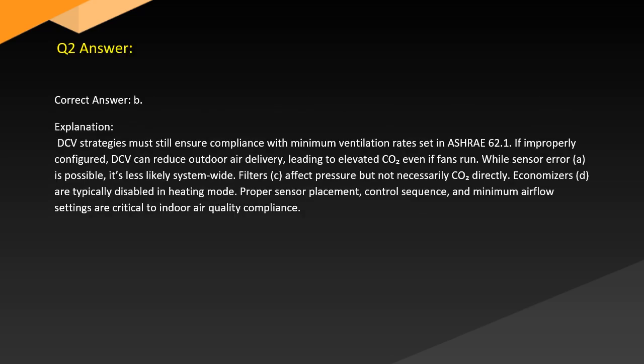Answer. Correct answer: B. Explanation. DCV strategies must still ensure compliance with minimum ventilation rates set in ASHRAE 62.1. If improperly configured, DCV can reduce outdoor air delivery, leading to elevated CO2 even if fans run. While sensor error is possible, it's less likely system-wide.